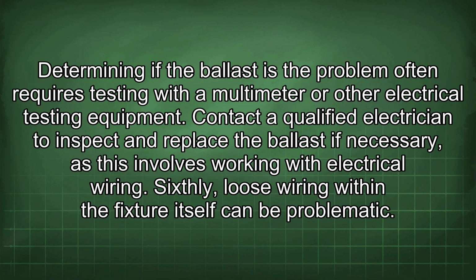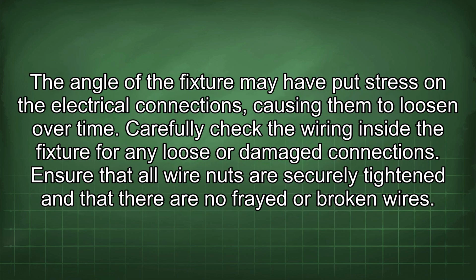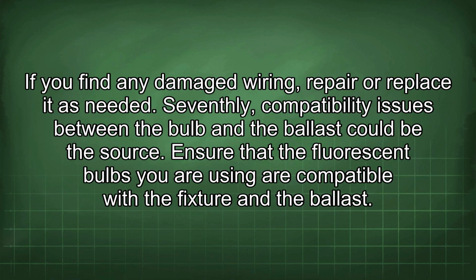Sixthly, loose wiring within the fixture itself can be problematic. The angle of the fixture may have put stress on the electrical connections, causing them to loosen over time. Carefully check the wiring inside the fixture for any loose or damaged connections. Ensure that all wire nuts are securely tightened and that there are no frayed or broken wires. If you find any damaged wiring, repair or replace it as needed.